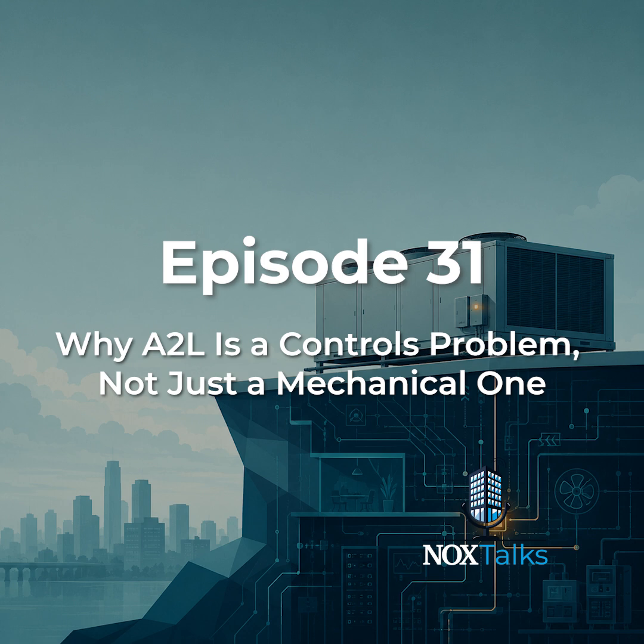So what do you actually do? Three things. First, inventory. Pull your chillers and rooftop units coming due for replacement, and for each ask, what refrigerant and safety class does the replacement model use? Does it need refrigerant detection? And does that detection interlock with my BAS? Or is it self-contained? That's a question for the manufacturer's applications engineer. A call to make early.